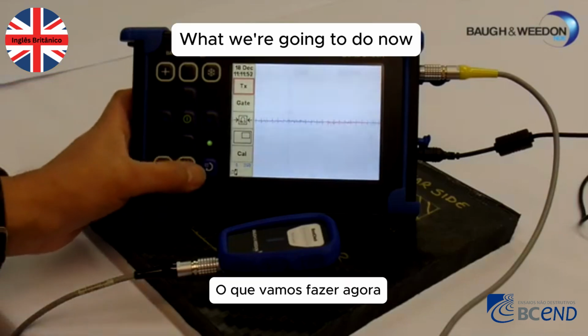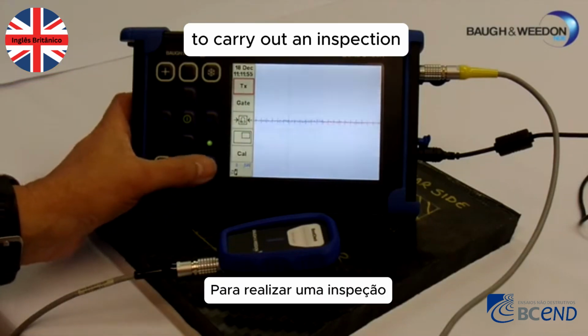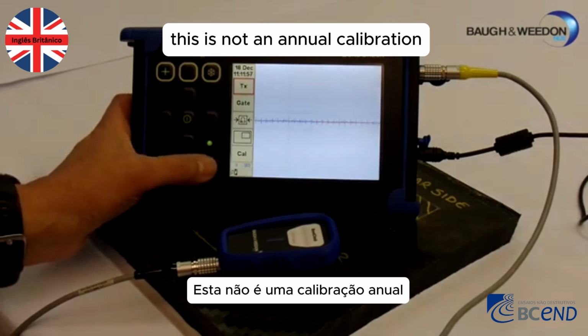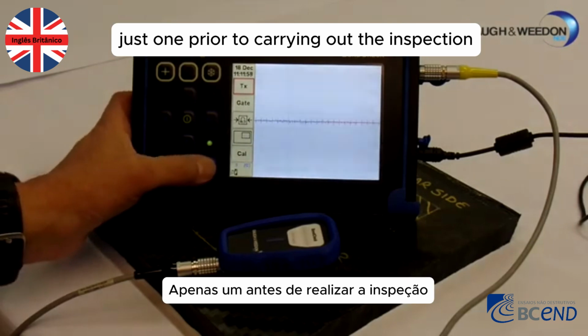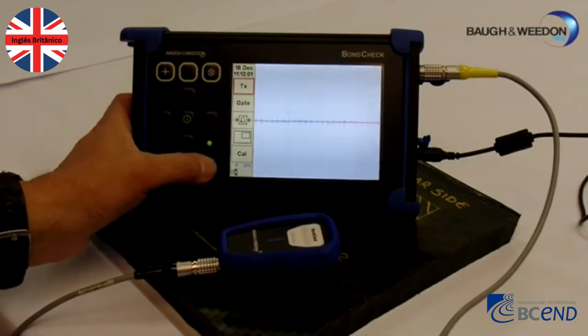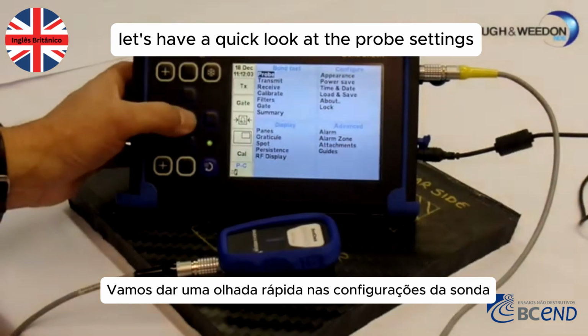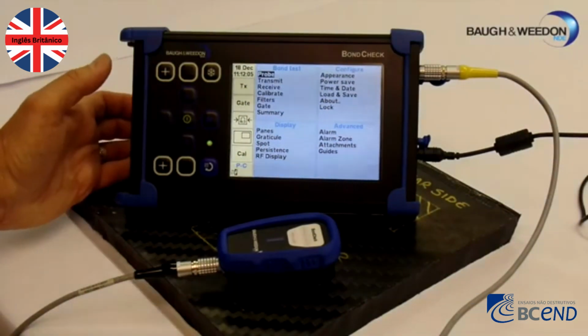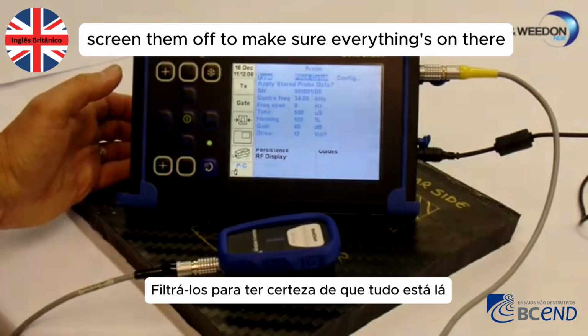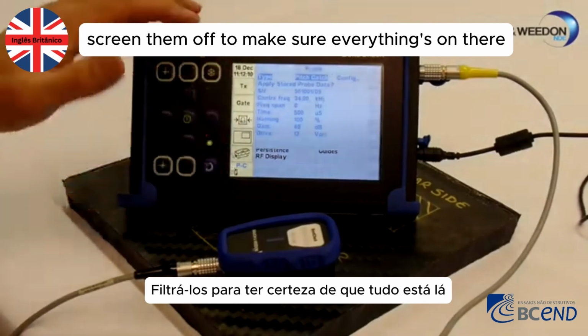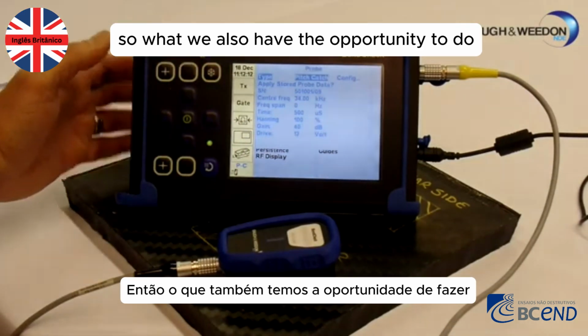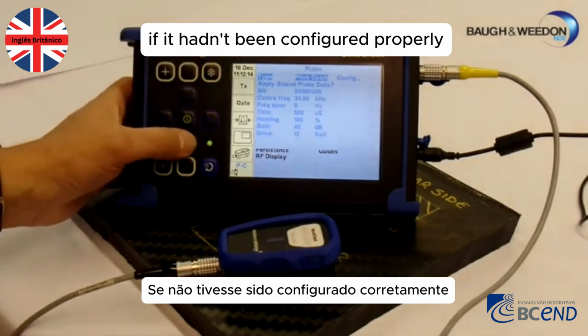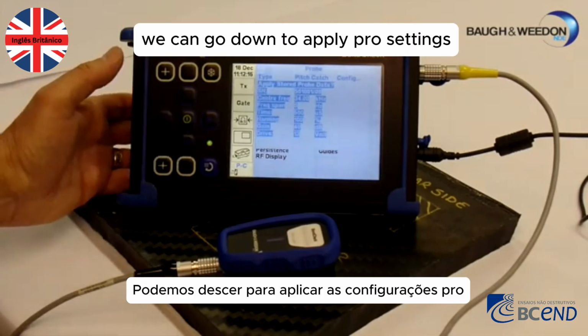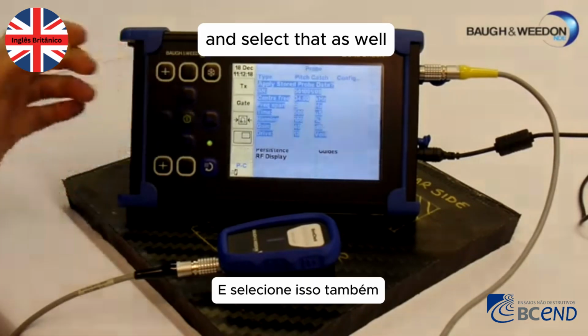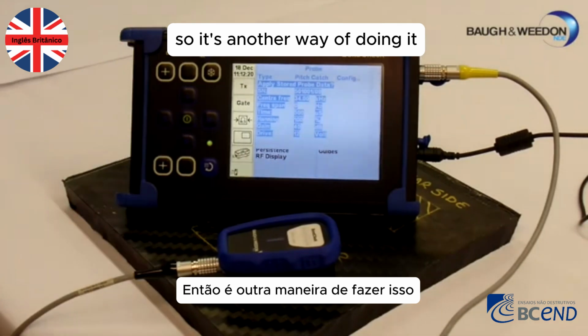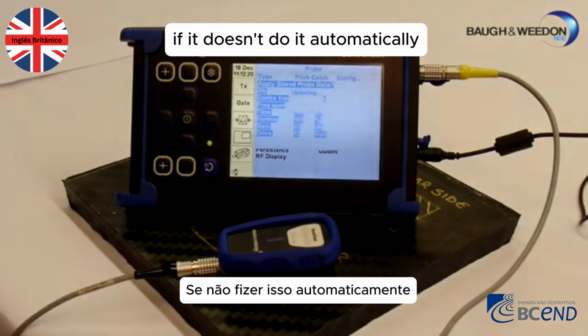What we're going to do now, prior to calibrating the unit to carry out an inspection, this is not an annual calibration, just one prior to carrying out the inspection. Go into the menu, let's have a quick look at the probe settings. Let's read them off and make sure everything's on there. What we also have the opportunity to do, if it hadn't been configured properly, is go down to apply probe settings and select that as well. So it's another way of doing it if it doesn't do it automatically.